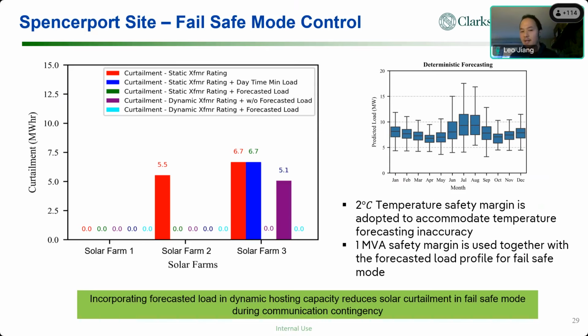This is a little bit of a busy slide. Basically, we did a number of scenario studies. We compared against the status quo, which is the red bar in the left figure here, the static transformer rating. That's what is currently implemented. The additional study that we did is based on all the real data we have, trying to understand what different combinations of updating the static hosting capacity to dynamic hosting capacity in the flex interconnection controllers mean for curtailment. But this one is really in the fail-safe mode control.